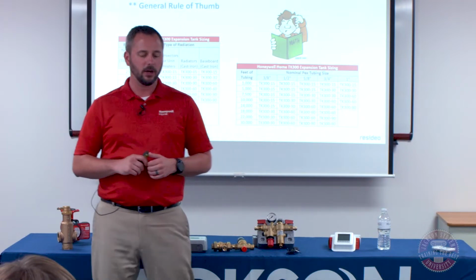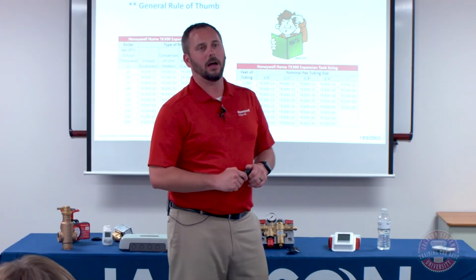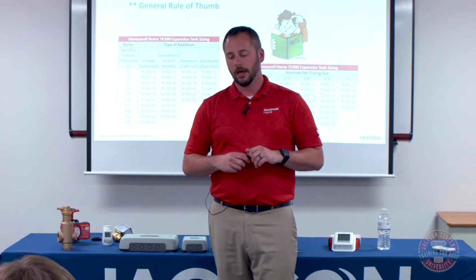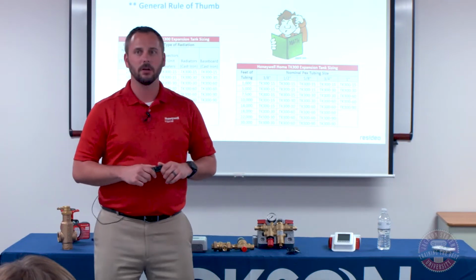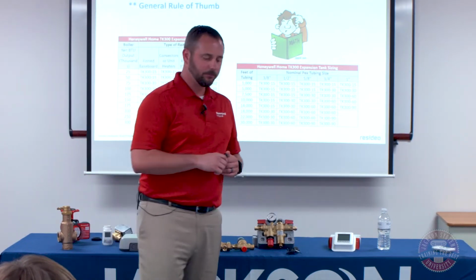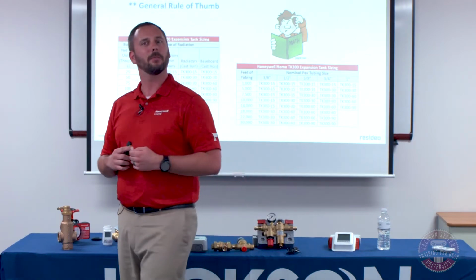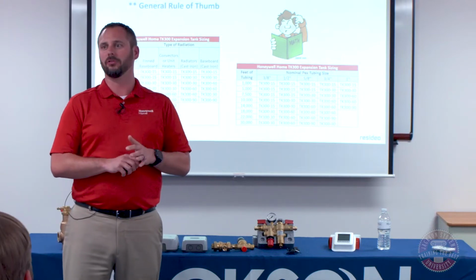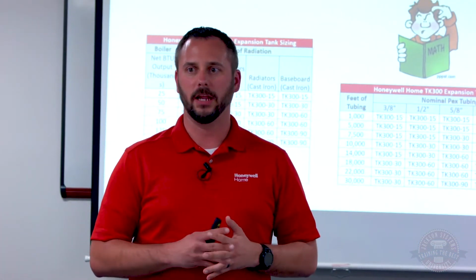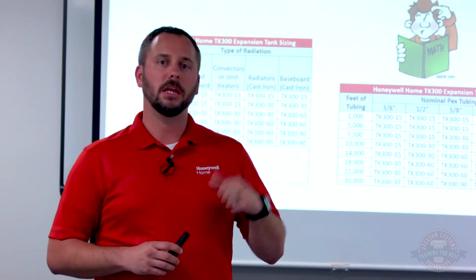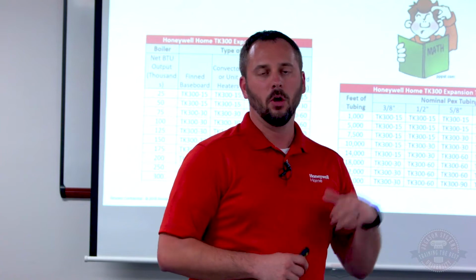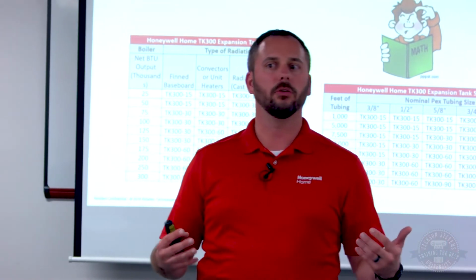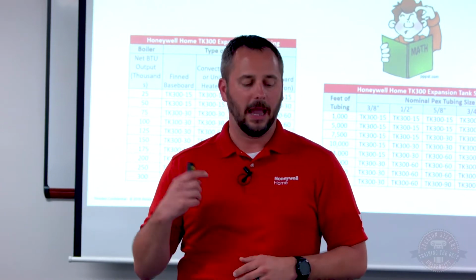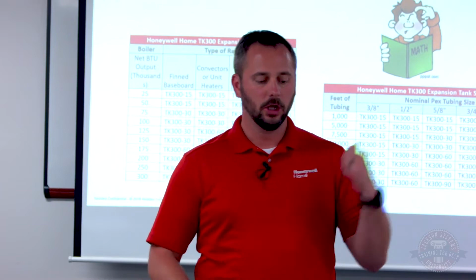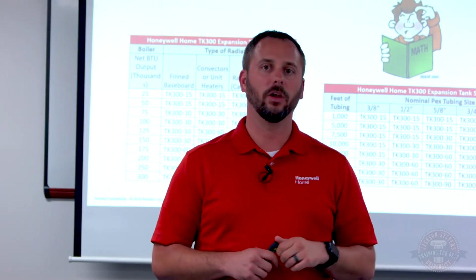So if you're not good at math, or let's say you're walking into an existing system where the relief valve is opening and pressures are bouncing up and down, I have some general rules of thumb that have been published that go through a couple of different situations. These are very safe numbers. Typically, these are grossly overstated, but it's something you can at least look off of. If you know how many BTUs the boiler is, look at the output rating of the boiler, not the input, and then look at what's being used. So is it fin tube, baseboard, radiators, etc.? This comes from the average temperatures used in those types of radiators, baseboard or heat emitters, as well as the average water volume inside of them. So you can use this based on what's doing the heating, as well as the output of the boiler.